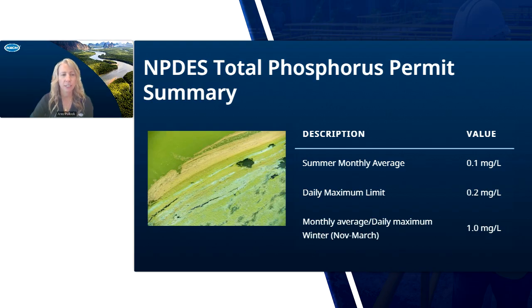Prior to the installation of the online phosphorus analyzer, the plant was running blind and behind, with once-a-day, 24-hour composite samples with results not available till late to mid-morning. Chemical dosing was set it and forget it, or overdosing to catch up when hit with high phosphorus loads at the influent. After the installation of the online phosphorus unit, the EZ Series analyzer provided early warnings of phosphorus spikes, allowing operators to take proactive action such as adjusting where and how much to dose that ferric chloride, along with adjustment of wasting rates to mitigate the impact.